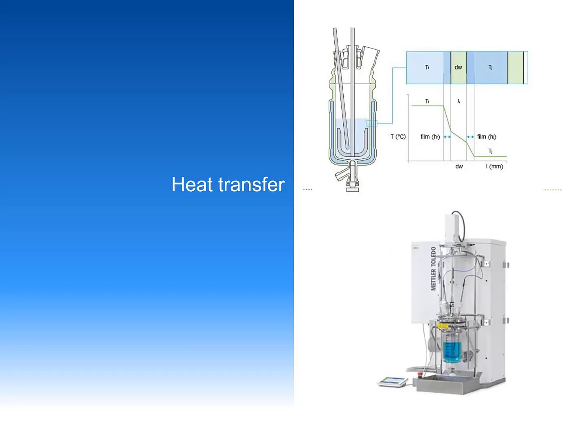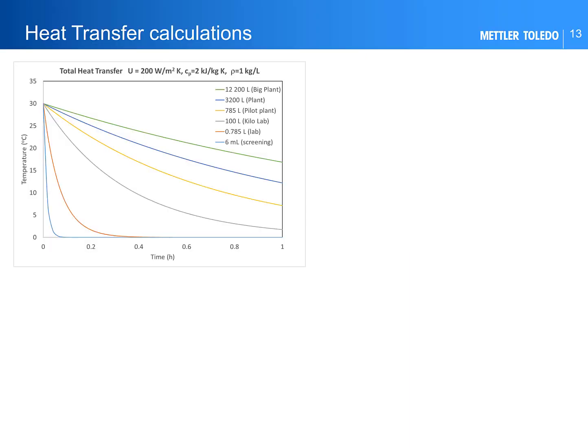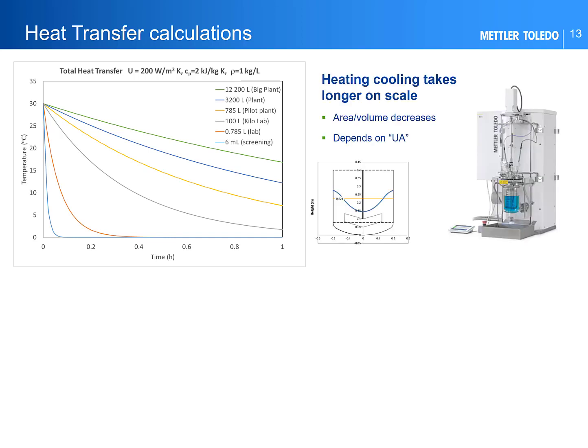Now I'll move on to talk about heat transfer, which is obviously important for safe operation on scale. As you're probably aware, the heat transfer performance generally drops as we increase in scale due to lower surface area per unit volume. The chart shows this for a range of scales — at small scale it takes a few minutes to cool from 30°C down to 0°C, whereas in a large vessel this can take several hours. This is related to the UA of the vessel.